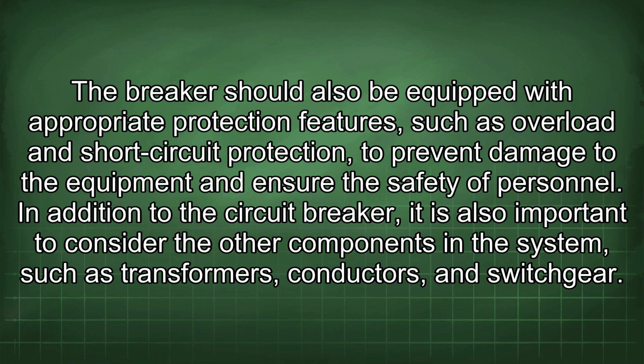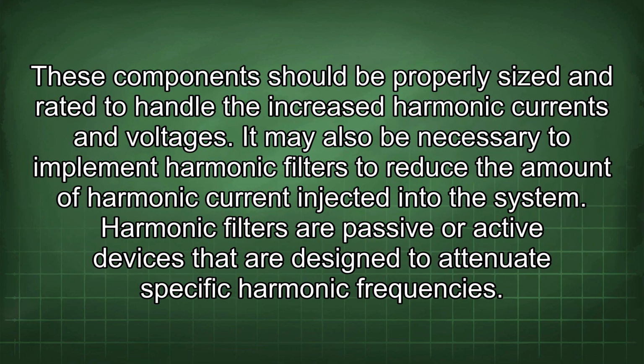In addition to the circuit breaker, it is also important to consider the other components in the system, such as transformers, conductors, and switchgear. These components should be properly sized and rated to handle the increased harmonic currents and voltages. It may also be necessary to implement harmonic filters to reduce the amount of harmonic current injected into the system.